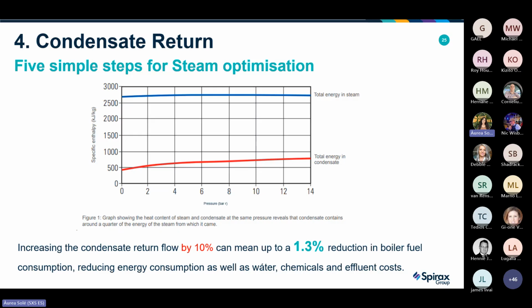So not only are there energy and cost reductions here, we are also reducing water consumption as well as chemicals and effluent costs. Why is that? Because by reusing the condensate, we don't need to treat it again, adding chemicals into the treatment operation in the boiler house. Finally, recovering the condensate also helps eliminate visible steam plumes, improving your site's environmental image.